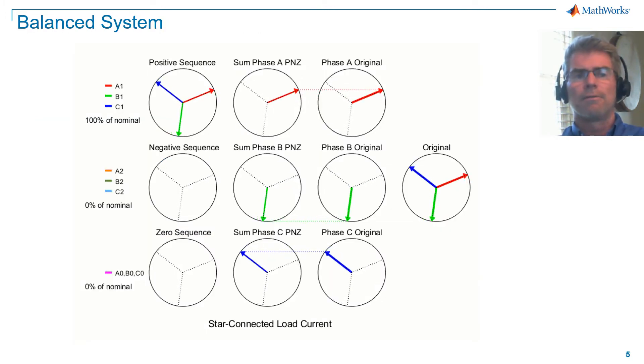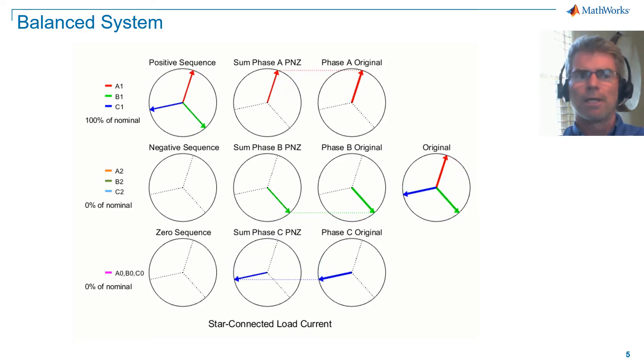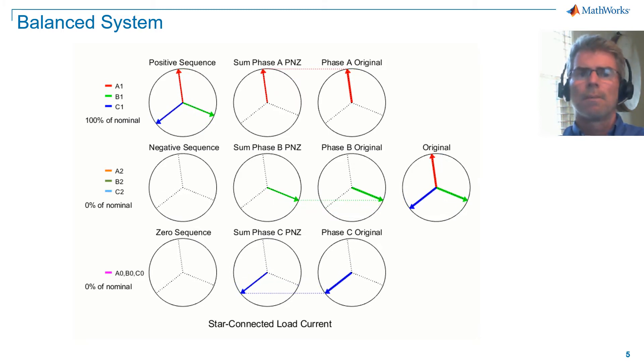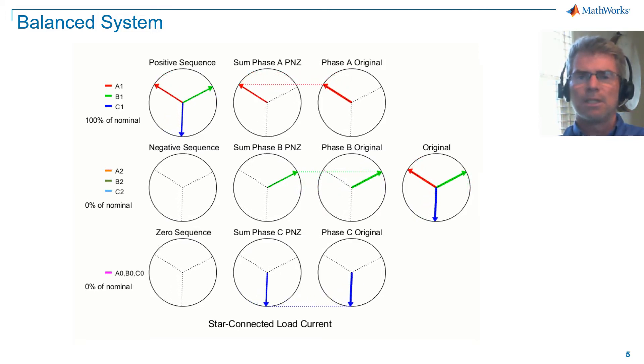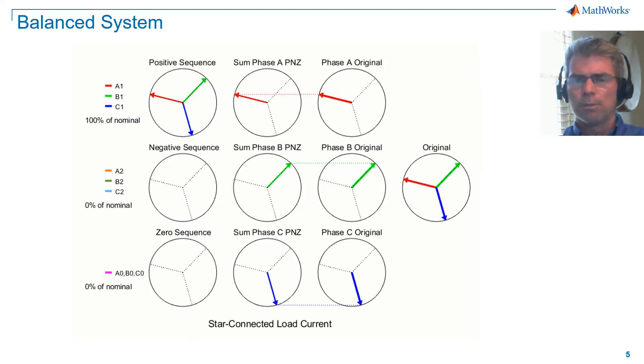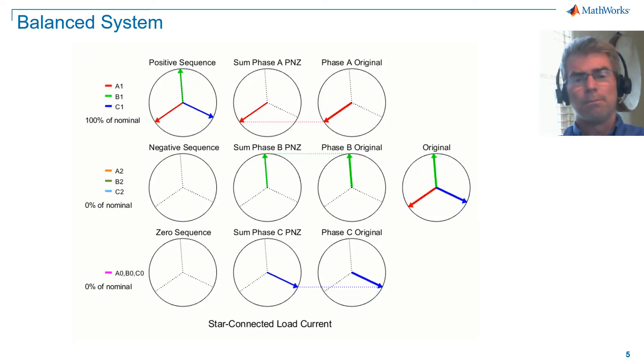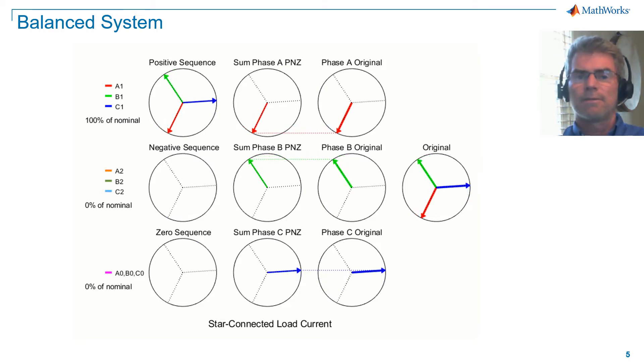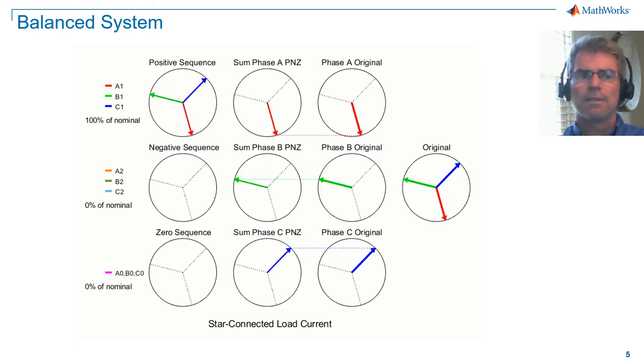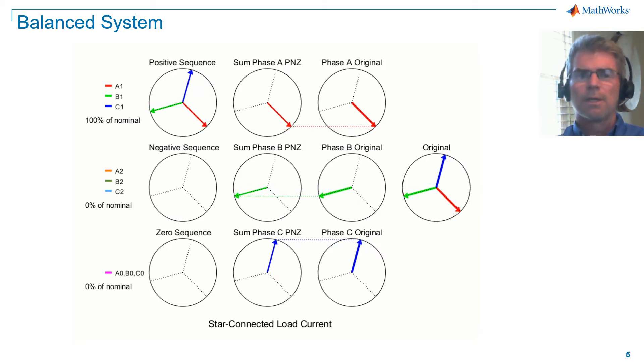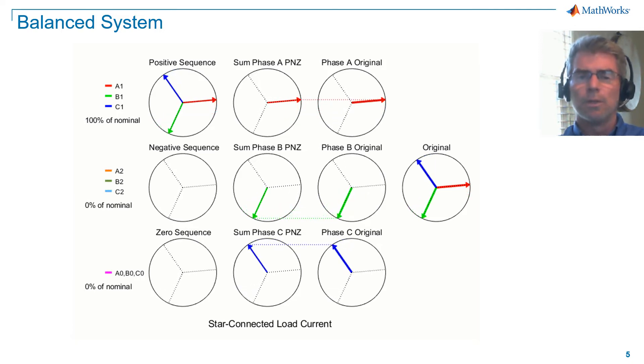Here is a visualization of symmetrical components for balanced current. Let me orient you around what we are seeing and we'll go column by column. First, some nomenclature. Positive sequence components are appended with a 1: A1, B1, C1. Negative sequence with a 2: A2, B2, C2, and zero sequence with a 0: A0, B0, C0. The column on the left shows the sequence components — at the top is the positive sequence, the middle is the negative sequence, and the bottom is the zero sequence. Note that for a balanced system, only positive sequence exists, and the positive sequence is equal to the original vectors.